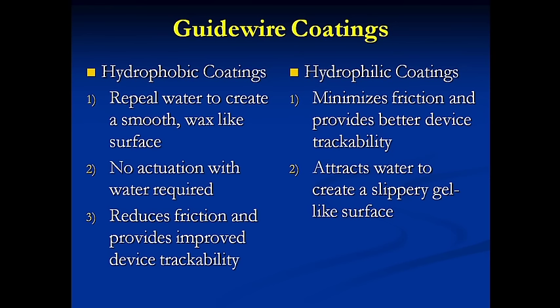Next comes the guide wire coatings. The two standard ones are hydrophobic coatings and hydrophilic coatings. So hydrophobic are the ones which repel water. So it creates a very smooth wax-like surface, and therefore you can pass devices very easily. You don't really need activation from water. It reduces friction, and as mentioned earlier, it helps with device trackability.